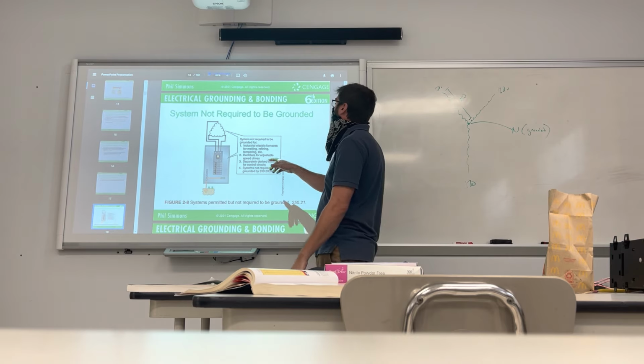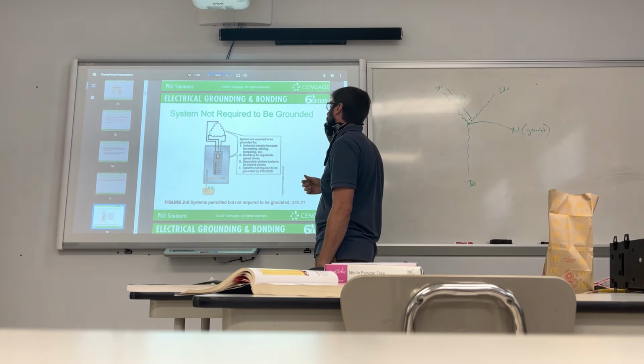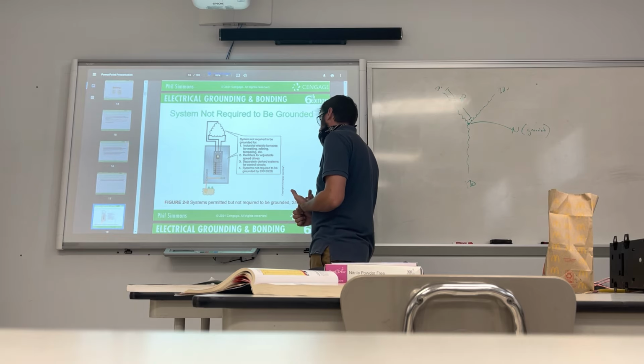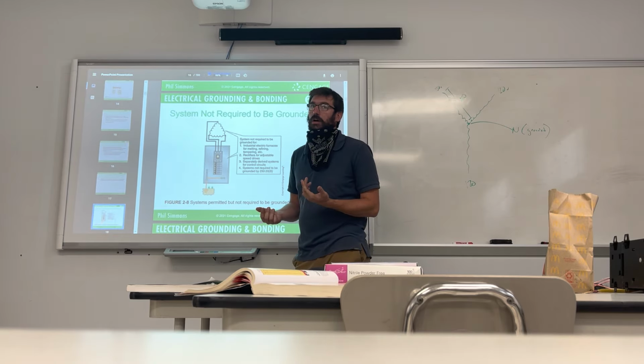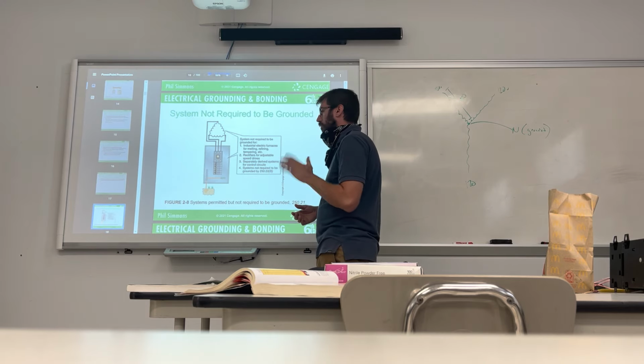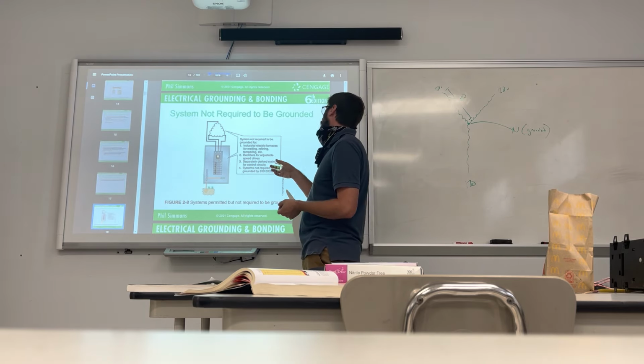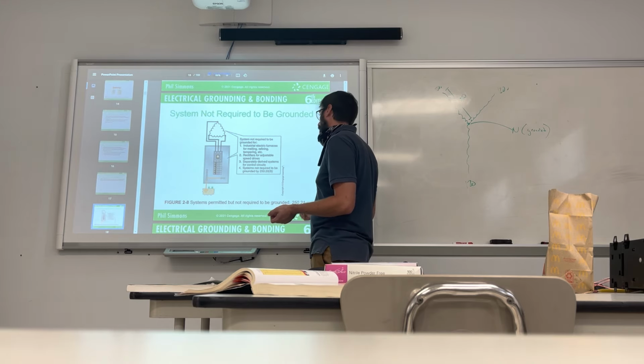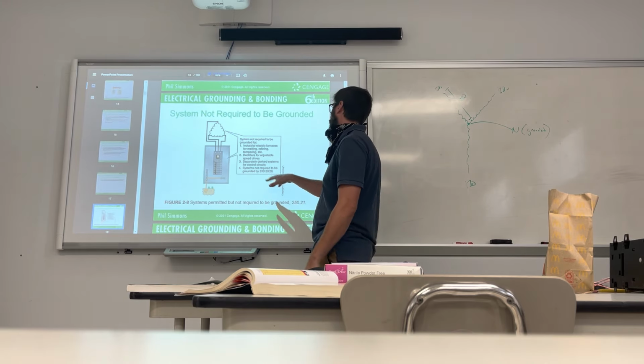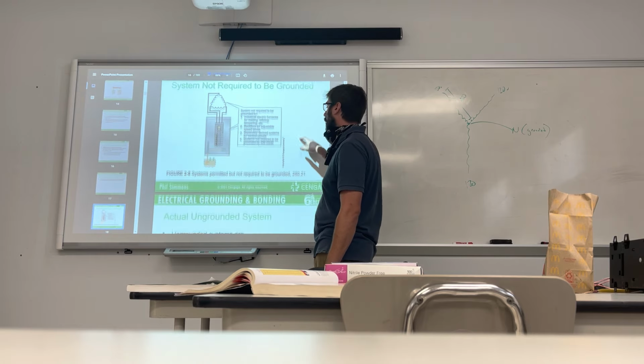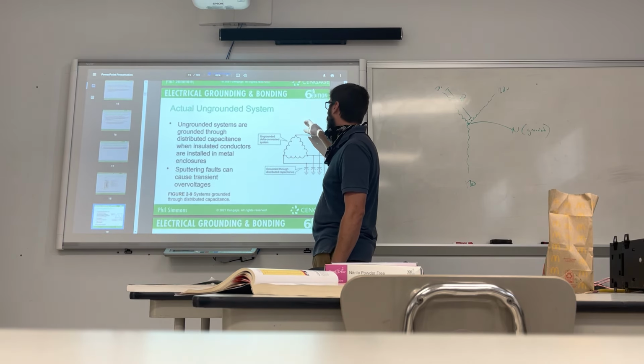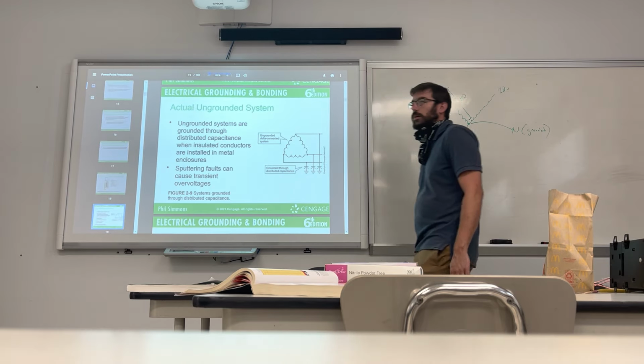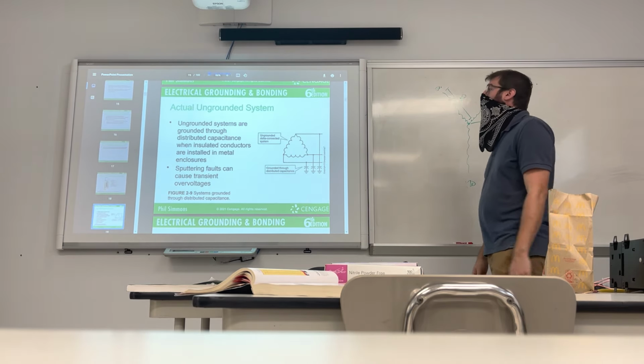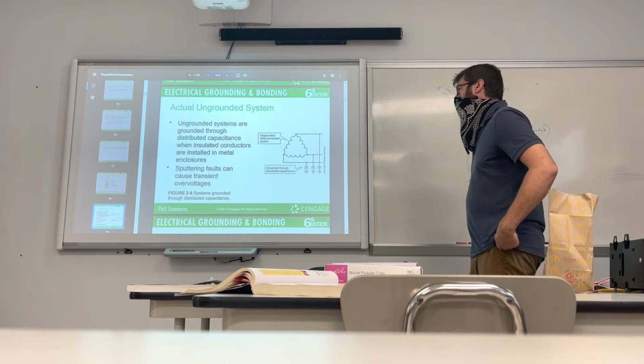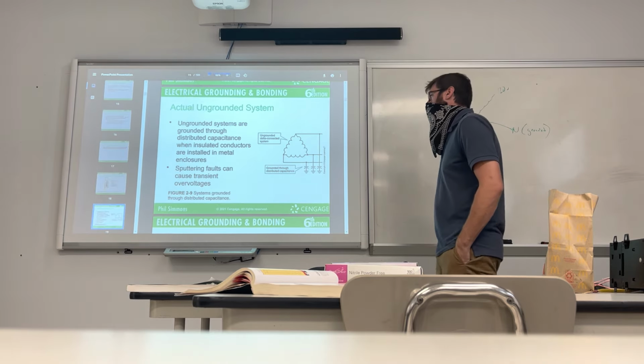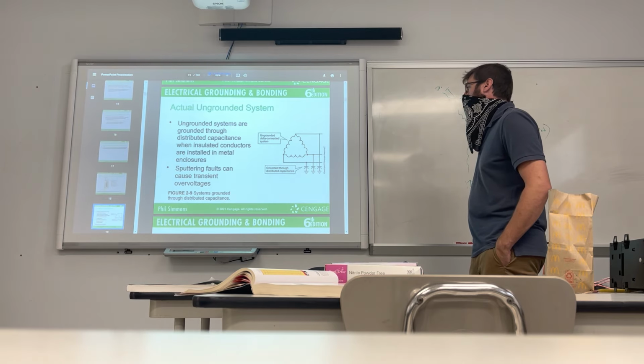So like we said before, industrial electric furnaces for melting, refining, and tempering, rectifiers for adjustable speed drives, which just means VFDs, which is just variable speed motor control. We'll talk about that next semester. Separately derived systems for control circuits, which is once again motor control, and the systems under 250.20(B). Actual ungrounded system: ungrounded systems are grounded through distributed capacitance when insulated conductors are installed in metal enclosures.